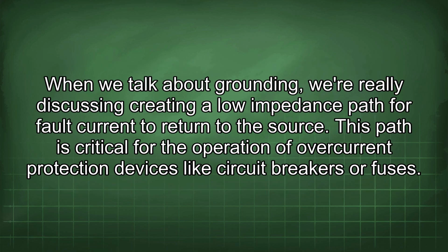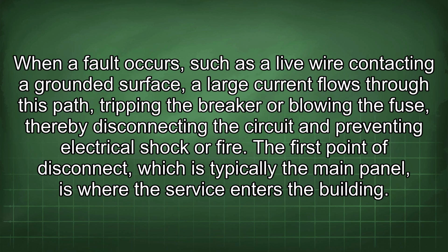When we talk about grounding, we're really discussing creating a low impedance path for fault current to return to the source. This path is critical for the operation of overcurrent protection devices like circuit breakers or fuses. When a fault occurs, such as a live wire contacting a grounded surface, a large current flows through this path, tripping the breaker or blowing the fuse, thereby disconnecting the circuit and preventing electrical shock or fire.